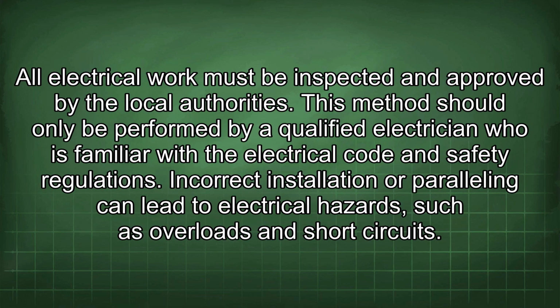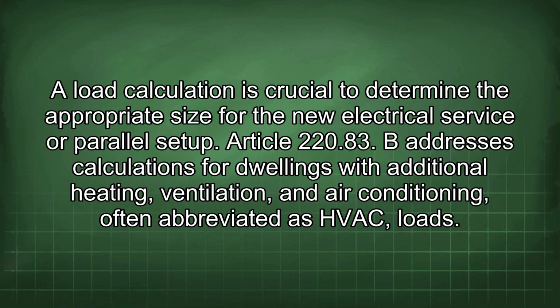All electrical work must be inspected and approved by the local authorities. This method should only be performed by a qualified electrician who is familiar with the electrical code and safety regulations. An incorrect installation of paralleling can lead to electrical hazards, such as overloads and short circuits. A load calculation is crucial to determine the appropriate size for the new electrical service or parallel setup. Article 220.83(B) addresses calculations for dwellings with additional heating, ventilation, and air conditioning, often abbreviated as HVAC, loads.